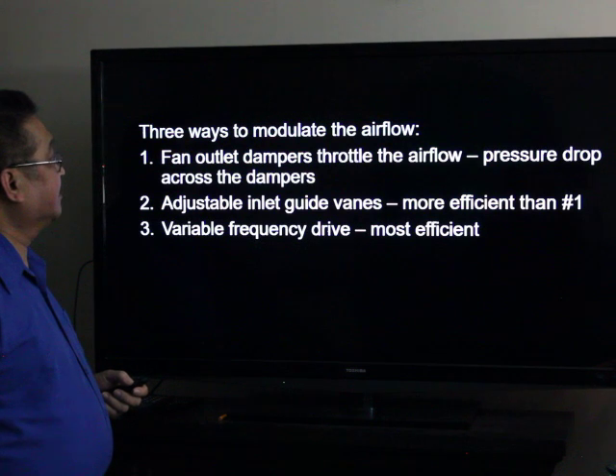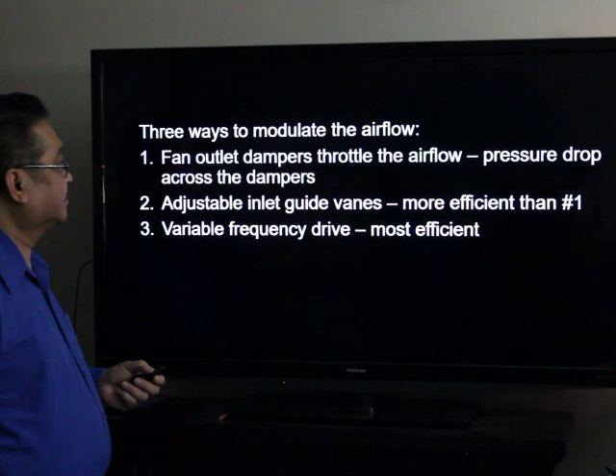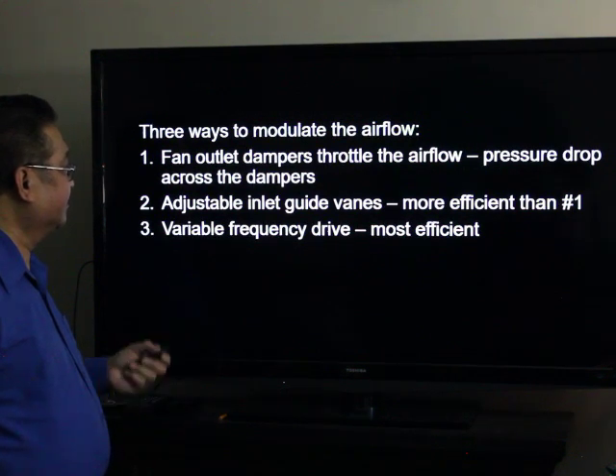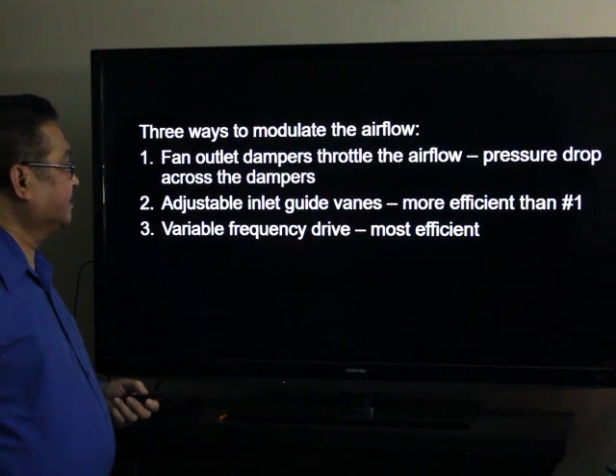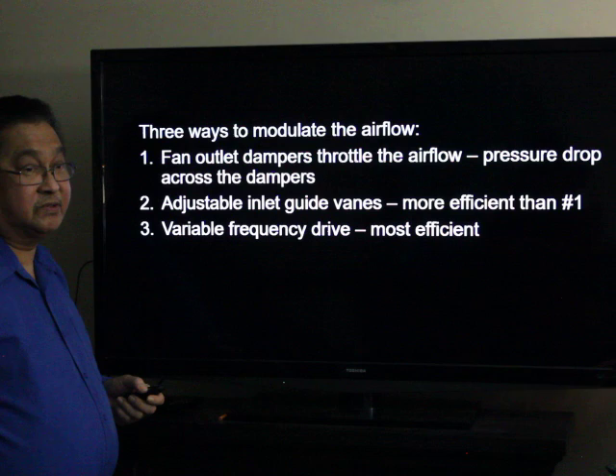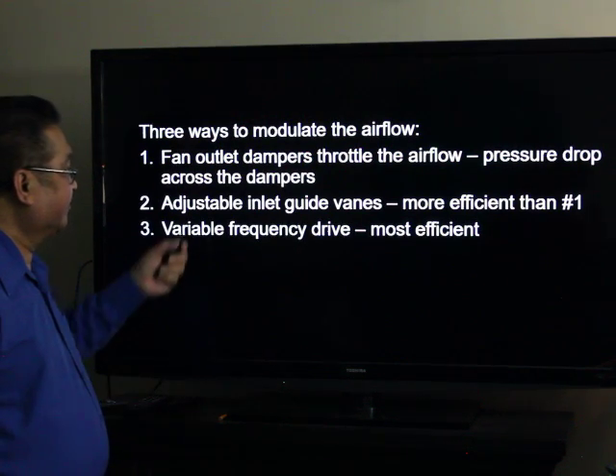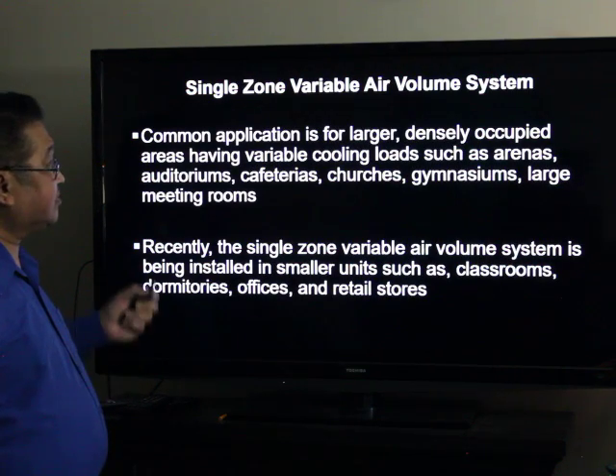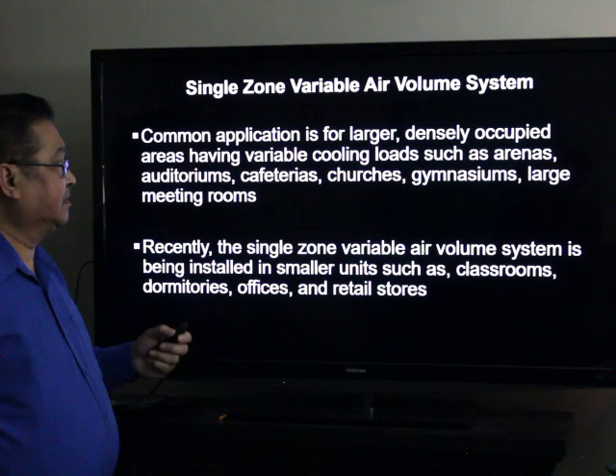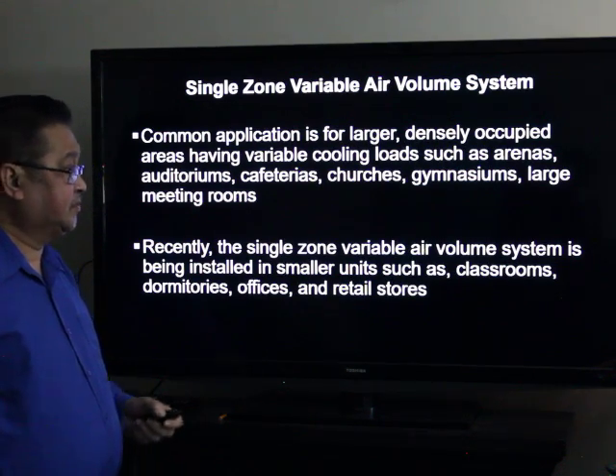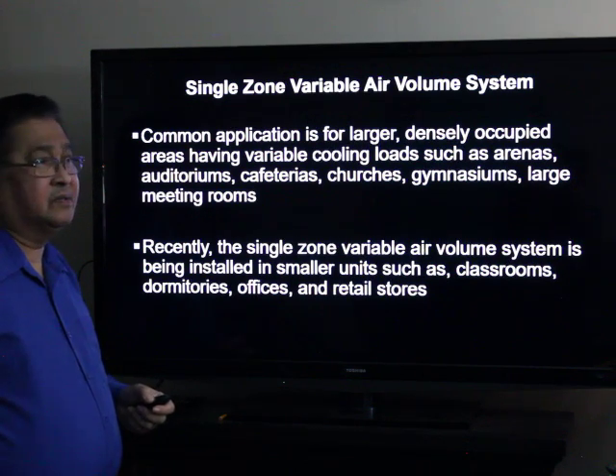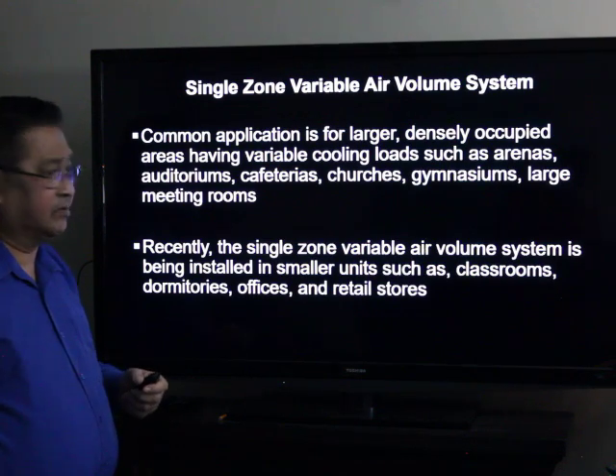There are three ways to modulate the airflow of the supply air fan. First, fan outlet dampers throttle the airflow, resulting in higher pressure drop across the dampers. Second, adjustable inlet guide vanes (IGVs), which are more efficient than the first. Third, variable frequency drives, which are the most favored option. Common applications are for larger densely occupied areas with variable cooling loads, such as arenas, gymnasiums, auditoriums, cafeterias, churches, and large meeting rooms. More recently, single-zone variable air volume systems are being used for smaller classrooms, offices, dormitories, and retail stores.